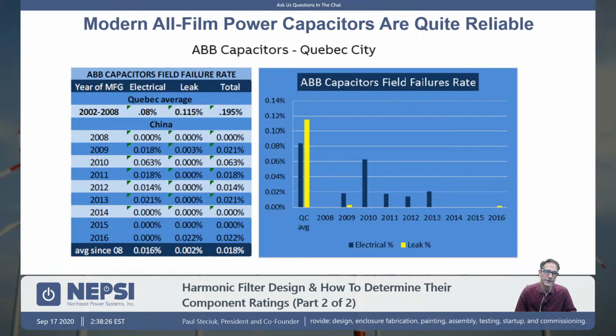When you look at the reliability of a capacitor, this is from ABB's presentation, the failure rates are very, very low. And if you properly rate the capacitor in the harmonic filter, you could expect failure rates of less than 1 in 5,000. So it's really very good failure rates. And this is data as presented by ABB once again. So less than 1 in 5,000.